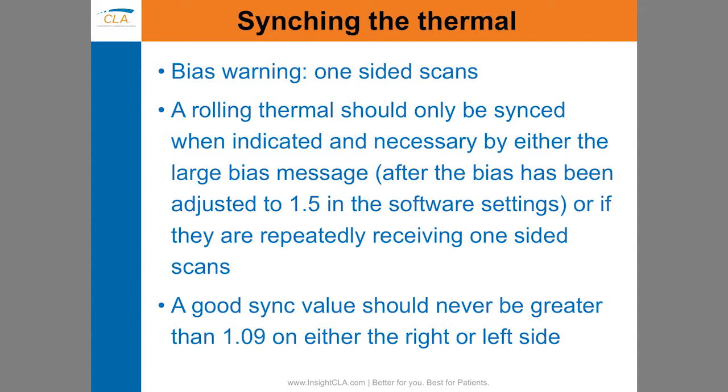Many of you ask about it. A good sync value should never be greater than 1.09 on either right side or left side. So we're moving it into the 9/100ths of a degree to keep those instruments in sync. I bring that forward because it's your responsibility to ensure that you're getting great data, and we built that in both in the software, and now you can sync it obviously yourself in-house. So it's a lovely feature that you can do.